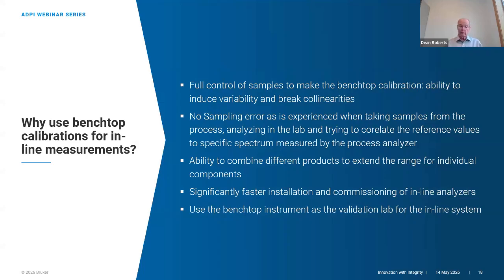And quite frankly, anybody that has developed a calibration by taking samples out of the process and using the spectrum developed by the process analyzer to develop the calibration knows how tedious a process that is. And quite frankly, it just makes the commissioning time for an inline analyzer so long as to be cost prohibitive. And that in itself is one of the reasons why people don't adopt inline analyzers. It also significantly speeds up the installation and commissioning of the system. So if we can start with a calibration that's going to work on all of the flow cells with all of the instruments for the same unit operation, then we can go in, we can put it in, and instead of calibrating the instrument, we're validating it. And we can get that done in a fairly short time.